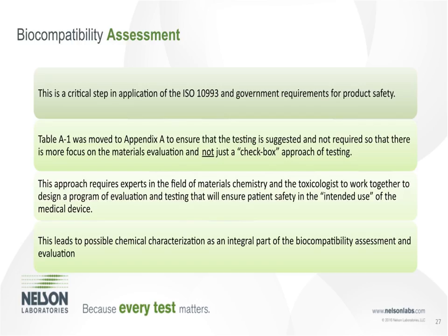Maybe the most important thing about this, and this is the biggest hurdle for some companies, is it no longer can be done just by some engineer or regulatory person just looking at that chart. That's the downside of this approach. Before, you just needed someone to basically read a chart and do the testing. Now it does put a little bit more emphasis on having experts in certain fields of chemistry, material chemistry, a toxicologist, a biocompatibility expert. These types of people should be involved in this risk assessment.